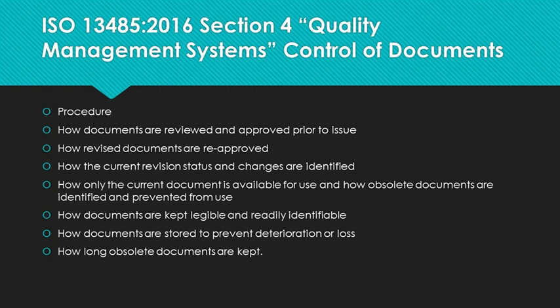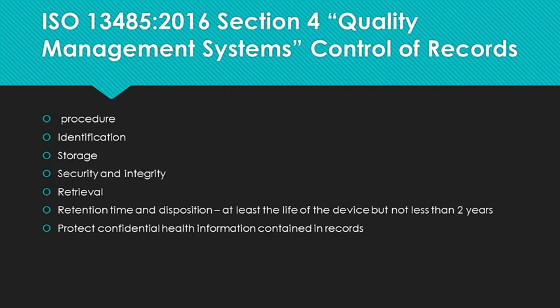Once the documents are controlled, your company needs to look at how it will control records. The easiest explanation I can give is a document tells how to do the process and a record shows exactly how you did the process. For example, a work instruction on how to weld a component to a medical device is a procedure; a form that records which welder, which personnel, and what lot of rod is used is a record. The records procedure should address identification, storage, security and integrity, retrieval, and retention time and disposal. The retention time must be the life of the device, but not less than two years. The procedure must also address how they protect confidential health information if it is contained in the records.